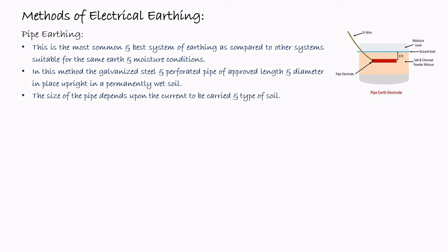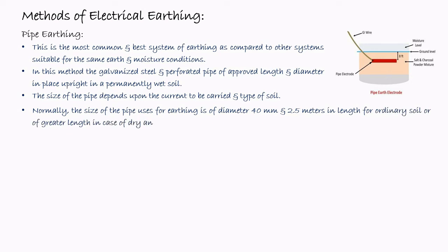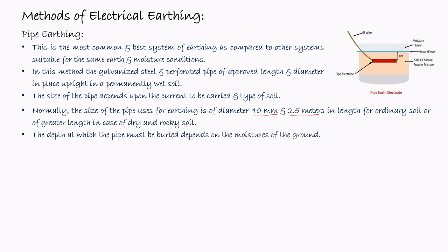The size of the pipe depends upon the current to be carried and the type of the soil. Normally, the size of the pipe used for earthing is 40 millimeter in diameter and the length is around 2.5 meter for ordinary soil, or greater length in case of dry and rocky soil. So for normal cases, the length should be around 2.5 meter and the diameter of the pipe around 40 millimeter, whereas if there is dry soil or a rocky area, then the length should be much more. The depth at which the pipe must be placed depends upon the moisture of the ground. The pipe is placed around 3.75 meters deep.